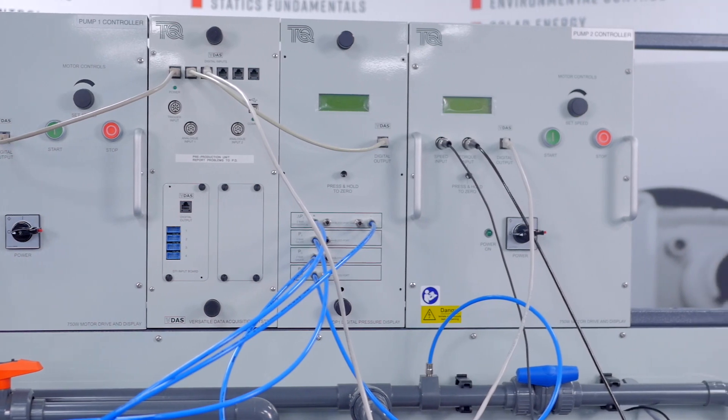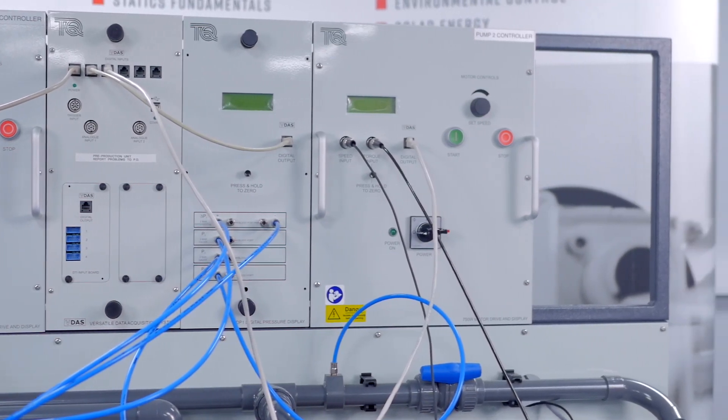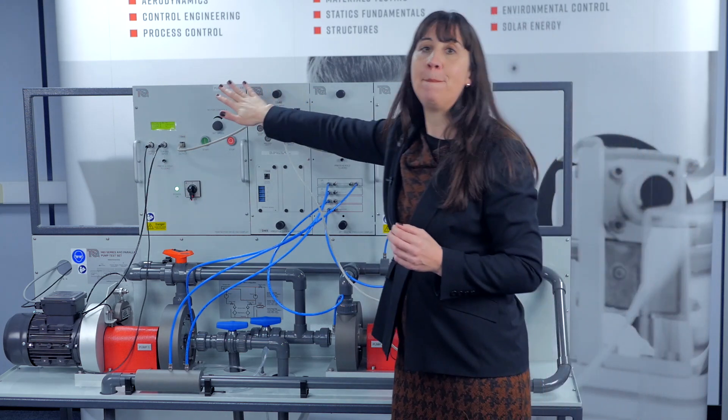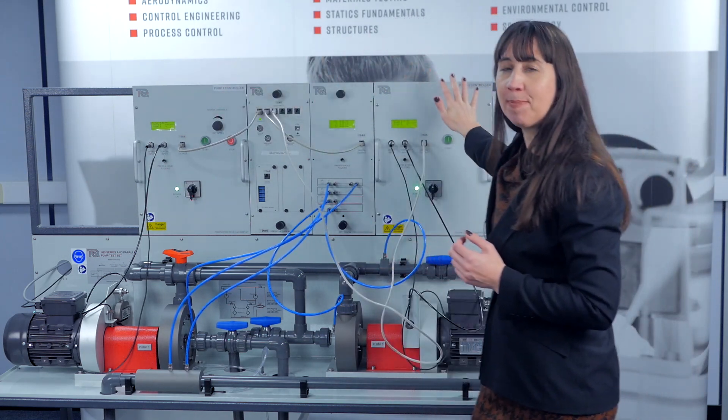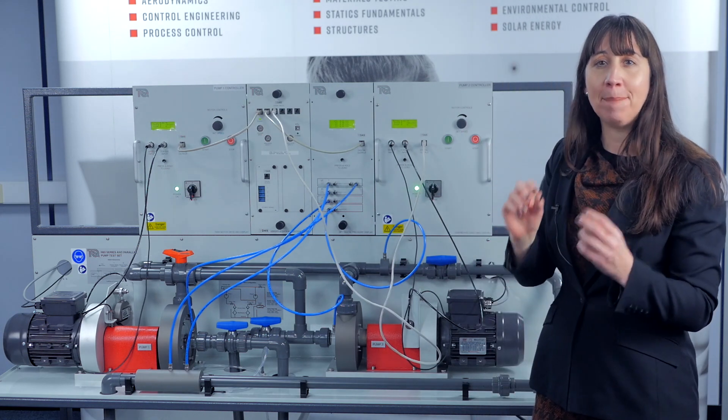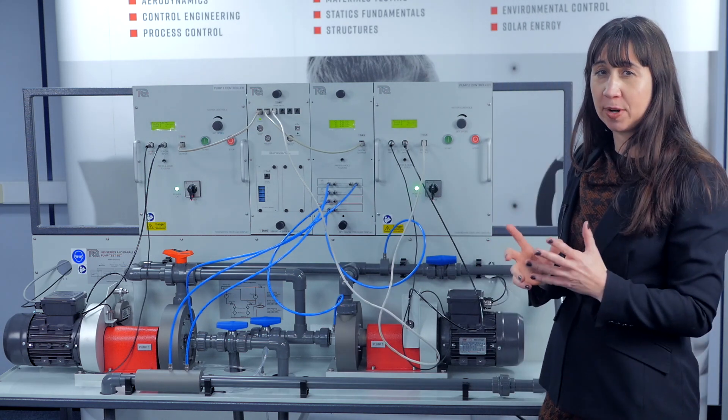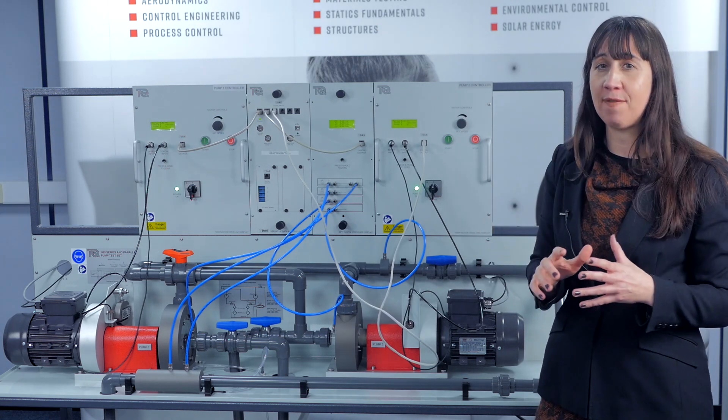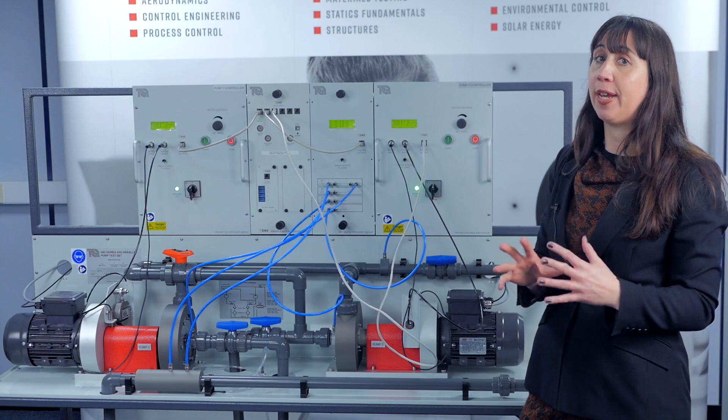Now let's look at the instrumentation and control modules that sit on the frame at the back here. Each pump has an electronic motor drive to control its speed, a load cell to measure torque, and a tachometer to measure pump speed. For extra safety precautions, each pump motor has a thermal sensor to stop the drive in the unlikely event of the motor overheating.